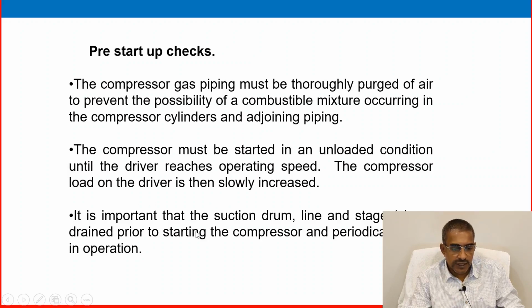It is important that the suction drum, line, and stages are drained prior to starting the compressor, and periodically while in operation. So, we almost always provide a drain system in the suction knockout drum and discharge knockout drum. In between, the casing drains will be there. So we have to drain all this properly before startup and periodically during operation.